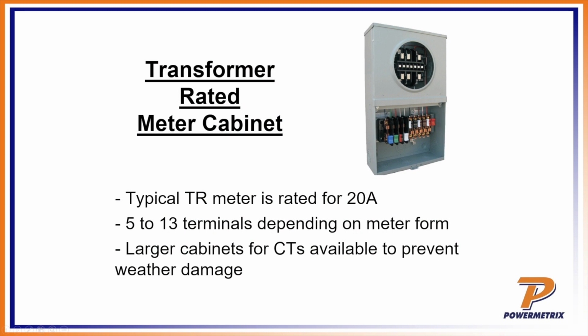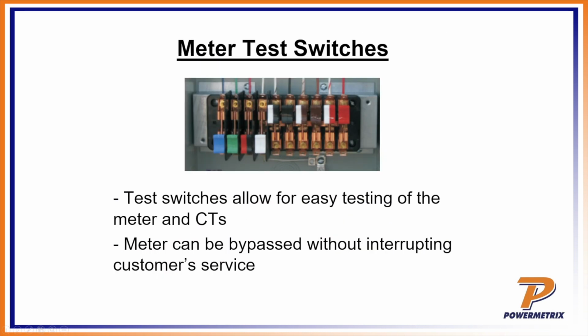That's what Steve's bringing up right there: you can have cabinets with the CTs within the cabinets, or you can have an external one where you've got just a CT cabinet sitting right beside the meter can. So you can do it different ways. But the important thing for us is it's a lot easier to work with those test switches when you're testing transformer rated meters, right? Yeah.